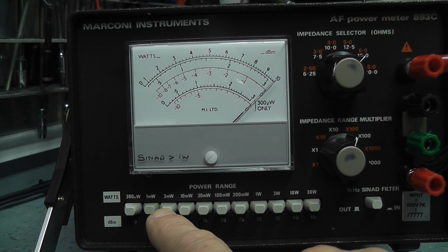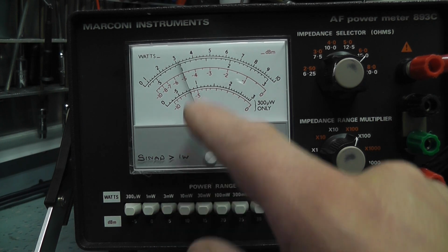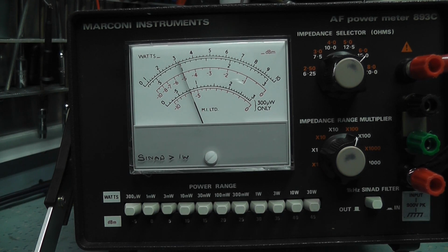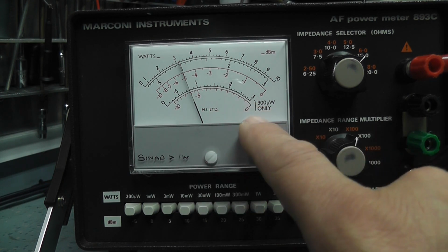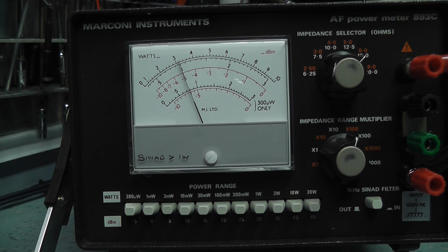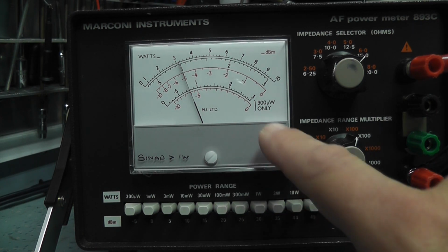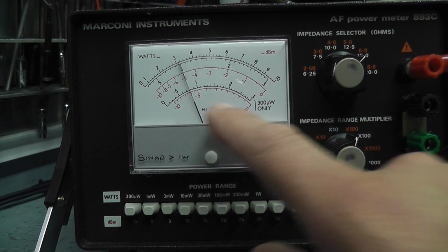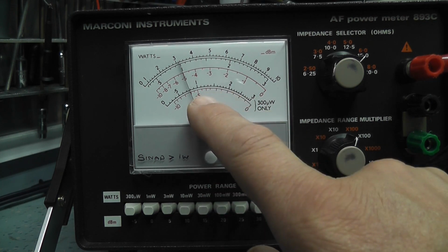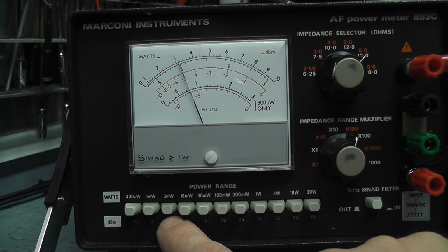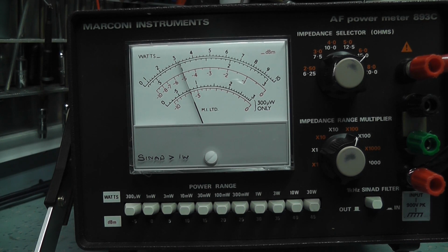We'll change to another range. Let's go to the 5 dBm range. Now you see it's slightly low there, but that's halfway down the scale. It's reading -7, and I'm still putting a 0 dBm level in. So it should be 5 dBm. It should be reading, what should it be? A 5 dBm and it's reading 0. Get my head around this now. Is that reading correctly or not?